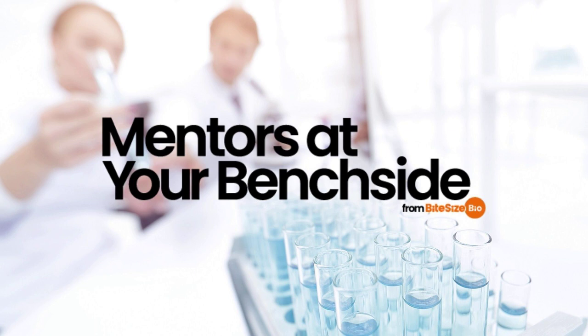Number 3. Use your pH meter correctly. Since the probe should always be wet, when you pH a solution you have 2 choices. Either you keep the probe submerged in your solution during pHing, or you take the probe out, wash it in deionized water, blot it gently with paper, put it in the storage solution, and wash it again before putting it back into your solution. The first choice is fine, but care must be taken while using a magnetic stirrer not to smash the probe. A medical student in our lab smashed the probe to pieces during their first day. Not an auspicious start.